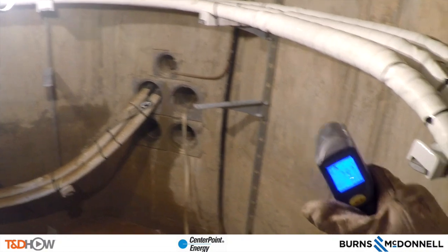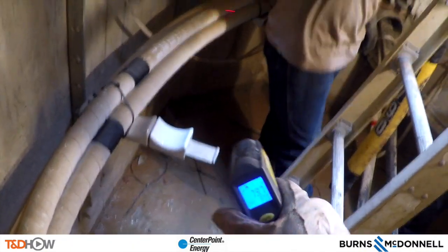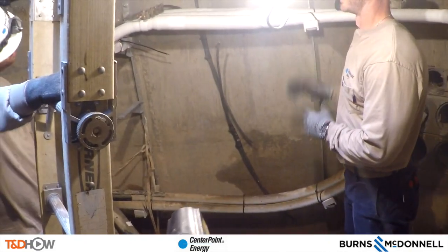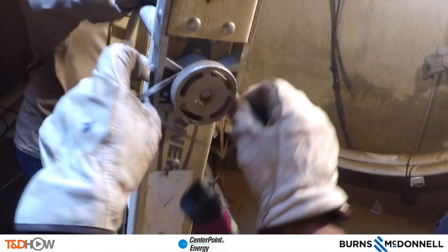Thermal imaging is being used to test for any hot spots underground — this was also done at the start of the job. We are now getting ready for part two of the underground cut around, which will be splicing the cables together. You have now seen part one: phase testing and cutting. Our participating utility was Centerpoint Energy, sponsored by Burns and McDonnell. In a moment you'll see those three cables ready for splicing. I am Jim Ducart with T&D How Videos — thank you for watching.